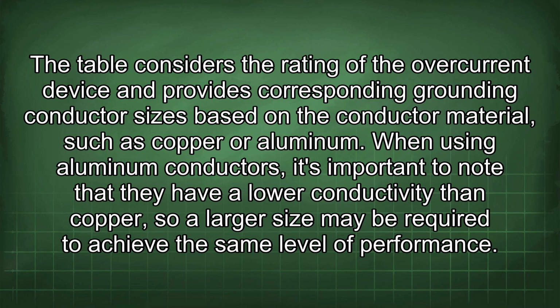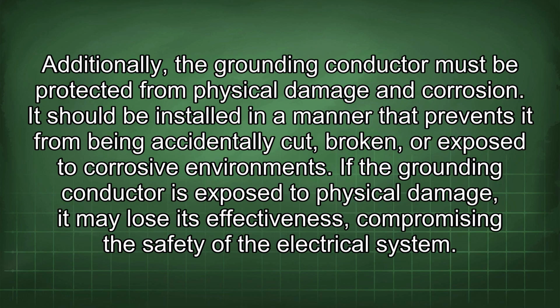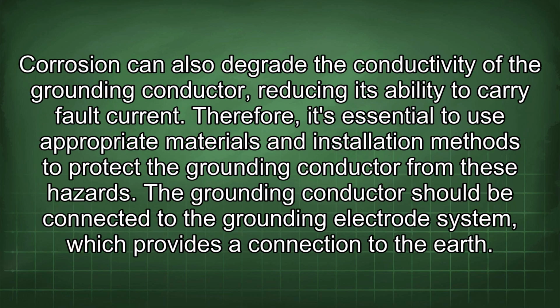When using aluminum conductors, it's important to note that they have a lower conductivity than copper, so a larger size may be required to achieve the same level of performance. Additionally, the grounding conductor must be protected from physical damage and corrosion. It should be installed in a manner that prevents it from being accidentally cut, broken, or exposed to corrosive environments. If the grounding conductor is exposed to physical damage, it may lose its effectiveness, compromising the safety of the electrical system. Corrosion can also degrade the conductivity of the grounding conductor, reducing its ability to carry fault current. Therefore, it's essential to use appropriate materials and installation methods to protect the grounding conductor from these hazards.